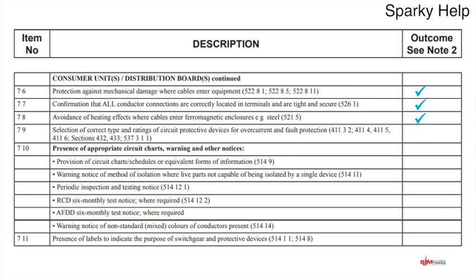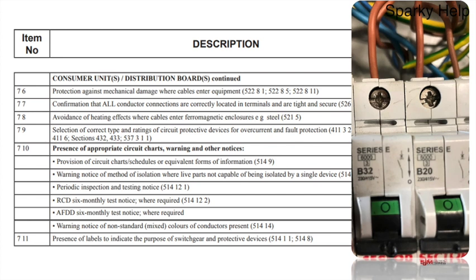Selection and correct type and rating of circuit protective devices for overcurrent and fault protection. Have we got the right size? So if we look at this, there's a B32 and a B20. But if we look at the cables going out, in this case I know they are 2.5s. Well, on the 20 amp at 2.5, perfectly acceptable. However, a 32 amp with a 2.5 cable going out, that is incorrect. So that would need correcting.